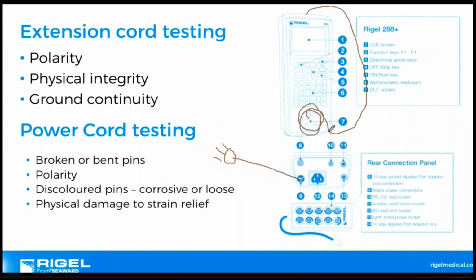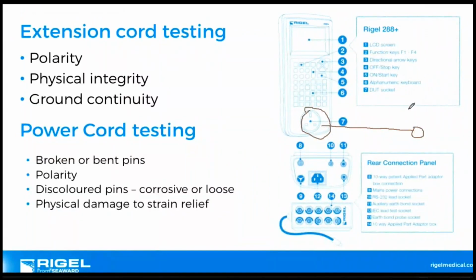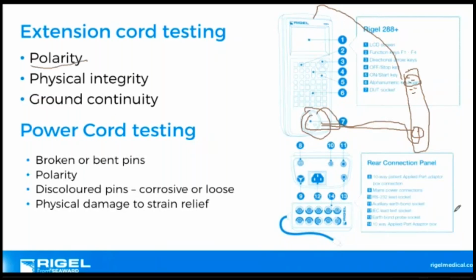Extension leads, actually, what you would do is you would have, I'll just draw that again. You would have your IEC lead or power cord lead going into an extension lead, etc. Sorry, that would be the other way around here. Now that's the plug going into this, and then you would have one of these plugs going into there, and that's how you can test extension lead for ground continuity or polarity, this type of thing. It also does an insulation test to make sure that it's electrically safe.